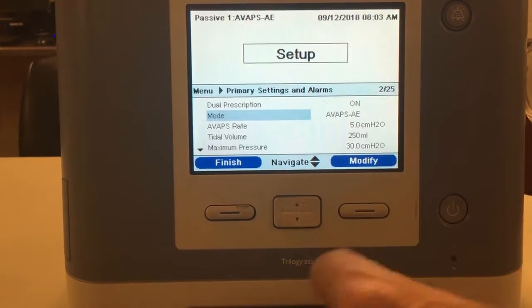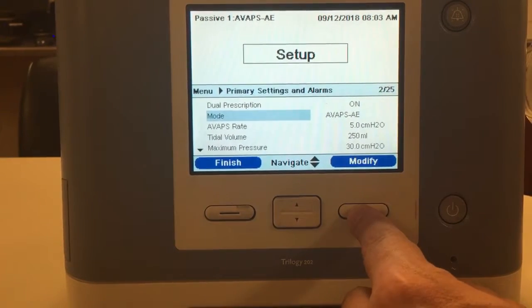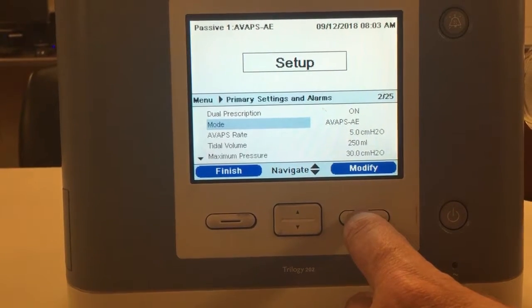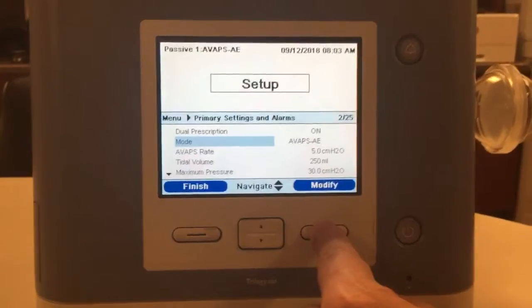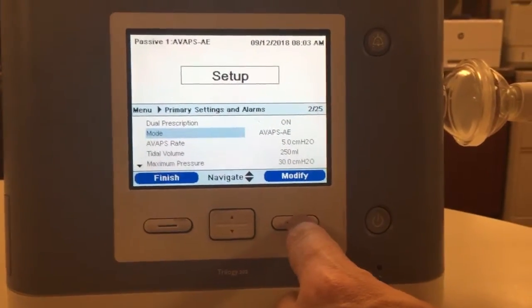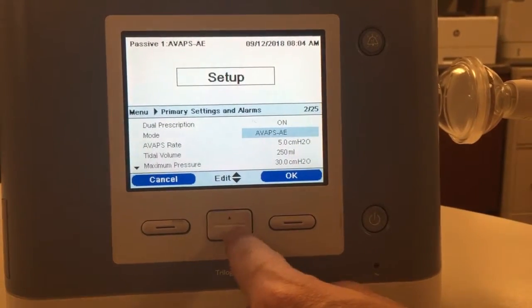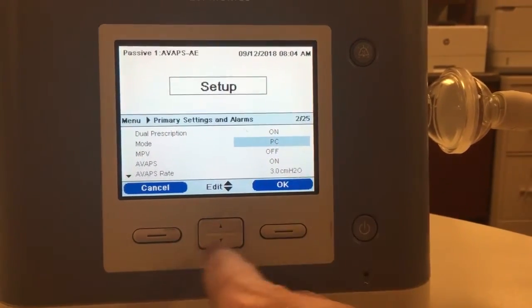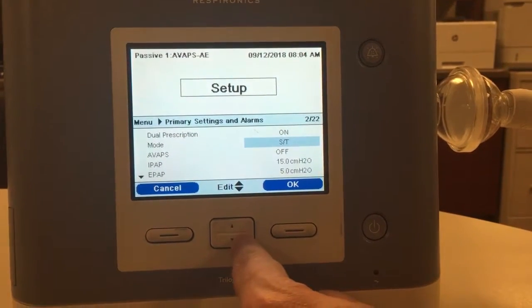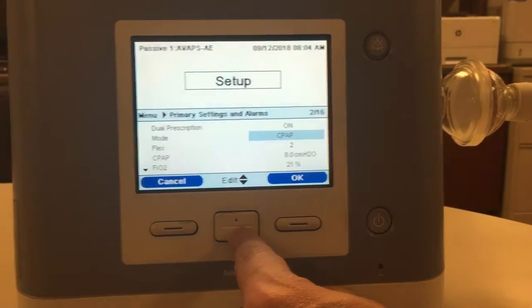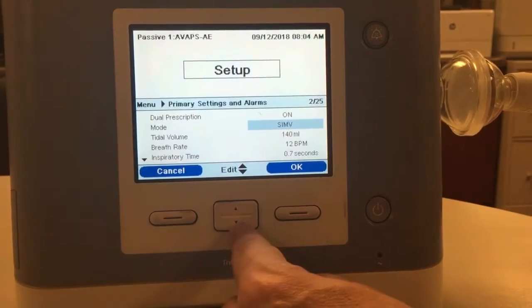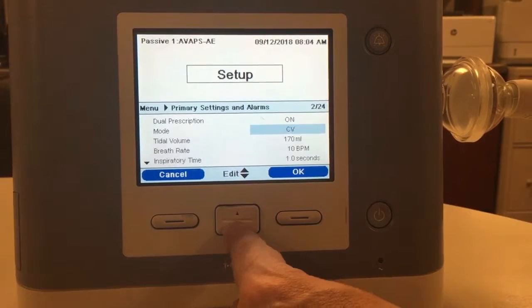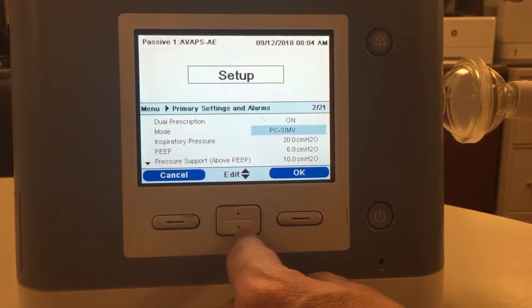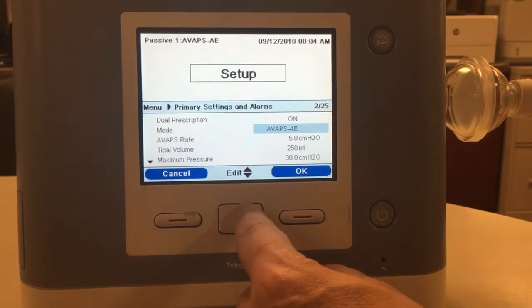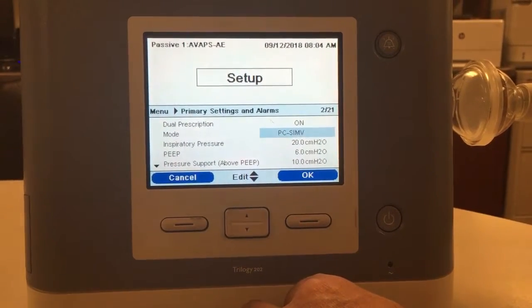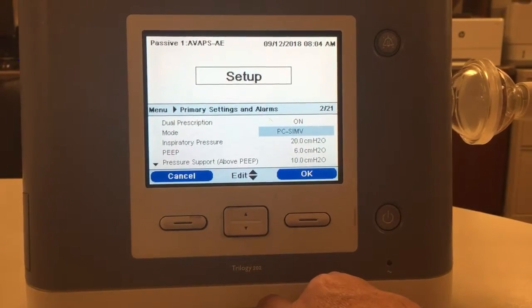Now to change a mode, you're in AVAPS AE. Let's say, for instance, a pulmonologist is not happy with AVAPS AE and wants to place the patient at SIMV pressure support. Just hit modify and scroll. You can scroll up or down, and you can see through all the modes: pressure control, a timed mode, spontaneous timed mode, spontaneous mode. Yes, this ventilator does do just CPAP. There's your SIMV mode, assist control mode, control volume mode, pressure control SIMV mode. So you can see that this ventilator has the capability of a critical care ICU ventilator. It has all those modes.